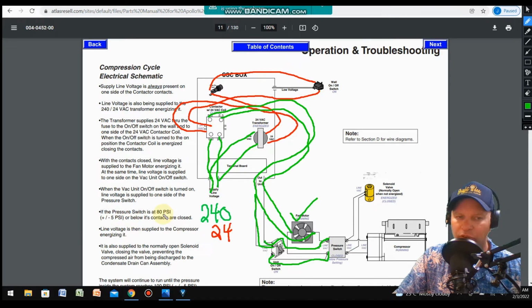on. So the contacts are closed. So we'll just imagine contacts being, and I'll just say what they mean by contacts is there's basically a line and there's like a little door, and that would be a depiction of an open contact, and then this would be a depiction of a closed contact. And so depending how you control that, it's either open, so that would be greater than 80 psi, and then it would be closed, which is going to be less than 80 psi.